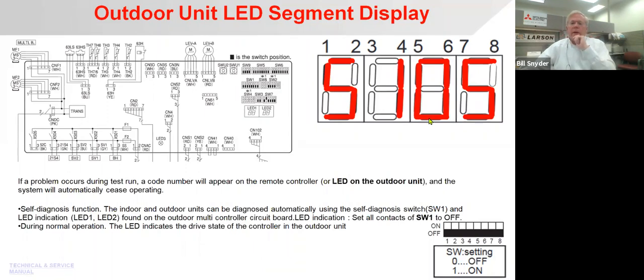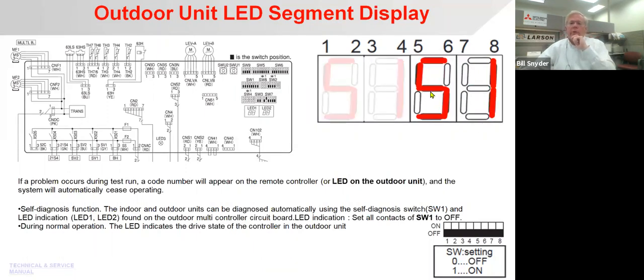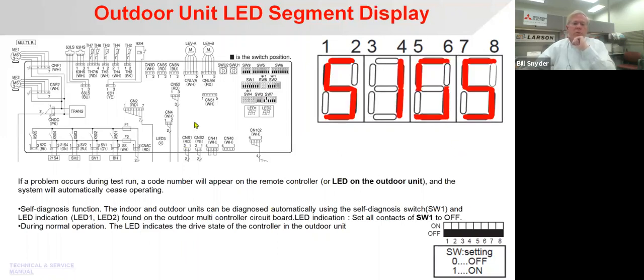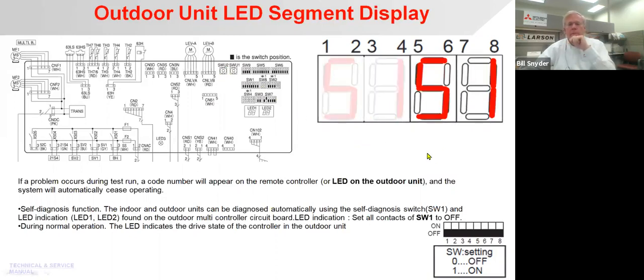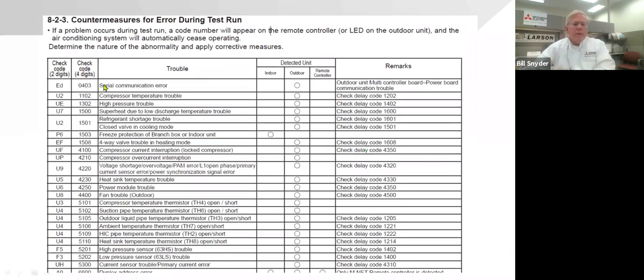5105 is the error code. 51 is where that error code is. That is the address. And if this outdoor unit here, right up here on these switches, was addressed to 51, that would mean that the error code 5105 was on the outdoor unit. If it was another address, it would be the indoor unit. So if you look it up in the service manual that's available on my link drive, these are your check codes. So 5105 is telling me that it's an outdoor liquid pipe temperature thermistor. TH3 is open or shorted.